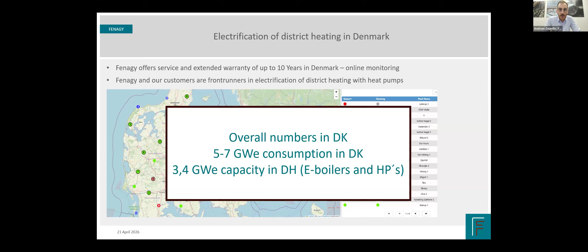When looking at district heating temperatures, there are significant differences, although that's not a limitation—I'd say it's more of an opportunity. Return temperatures are traditionally very low in Denmark, from 30 to 50, supply maybe from 60 to 90. And if we focus on air source heat pumps, ambient temperatures can be as extremely cold as -20, and then a good summer day of +25.